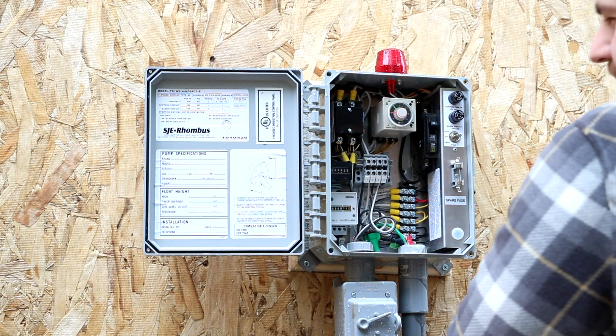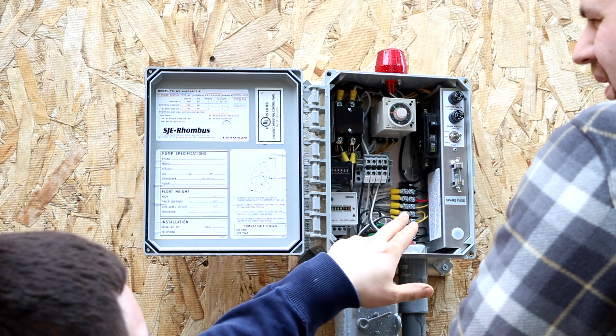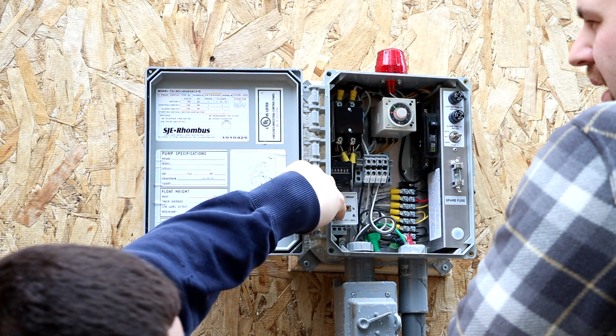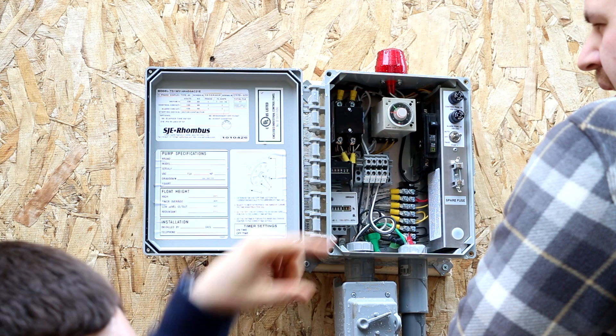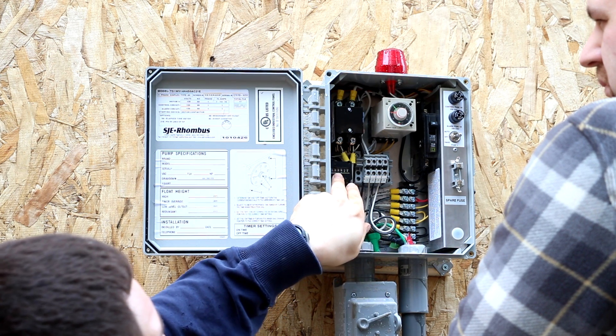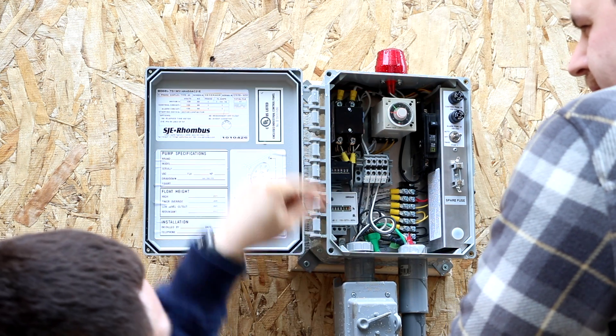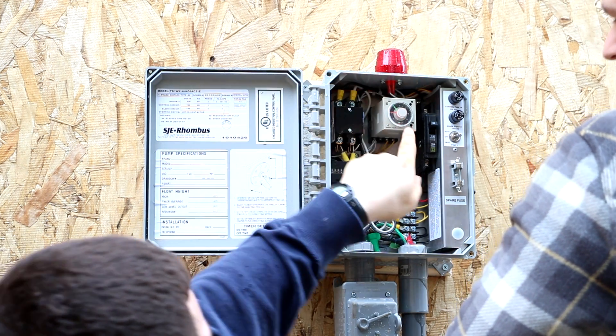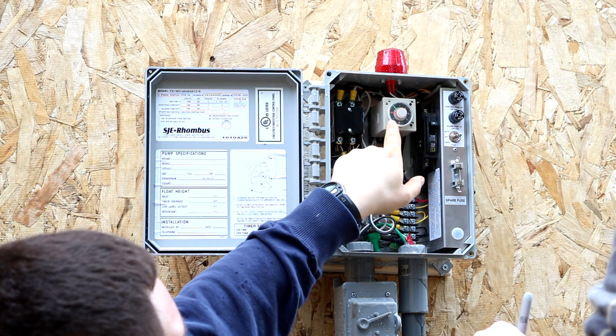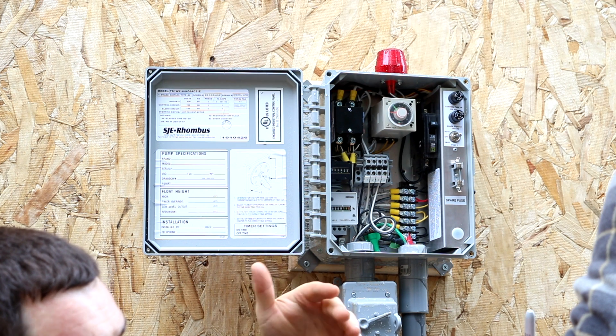We are setting the control panel up to make sure it works. It's currently electrically energized. Inside of here, you have an hour meter — this measures how many hours the pump has been running. This next meter up is cycle time, so how many cycles the pump has gone through. This is the timed dose meter, and this is what sets your pump to come on and off based on your septic design.